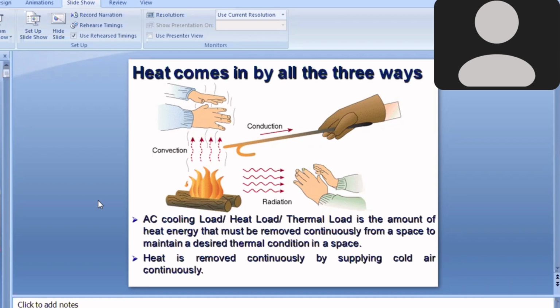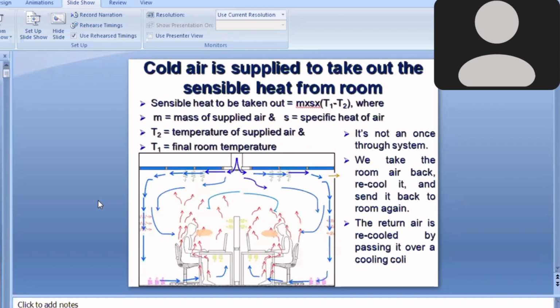And that we do by supplying cold air in the room. We supply cold air in the room, it picks up all the heat from within the room, and then it gets heated up and we take that air out. So this is how we supply the air inside the room. Say from the top of the ceiling we supply the air, it comes within the room, it picks up all the heat from the room, and then we take it out. So it takes away the heat. It takes away only the sensible part of the heat.